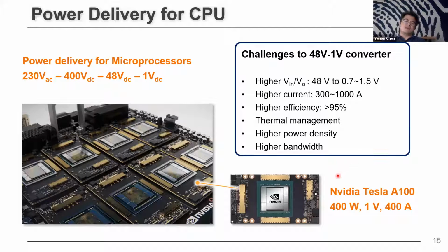This brings challenges to the 48 volt to 1 volt converter on the motherboard. First is the high voltage conversion ratio: you need to convert 48 volt down to 1 volt or below, like 0.7 volt. At the same time, you need to provide very high current at the output, while still maintaining high efficiency above 95%.